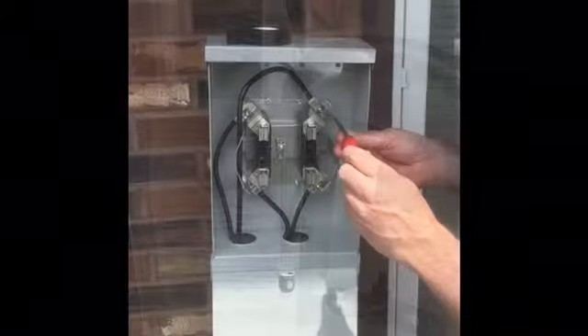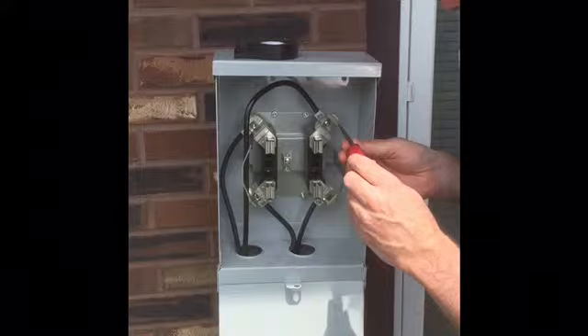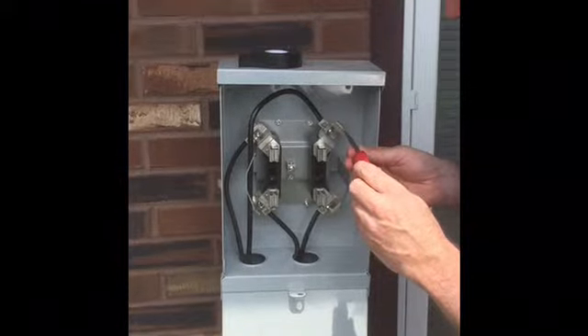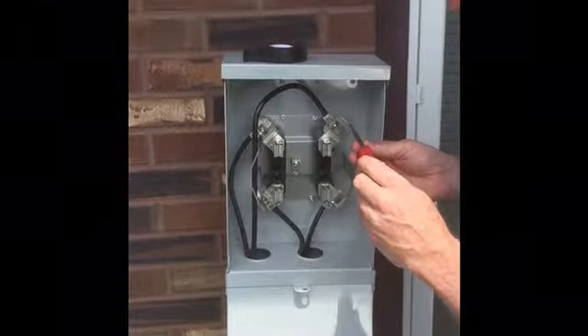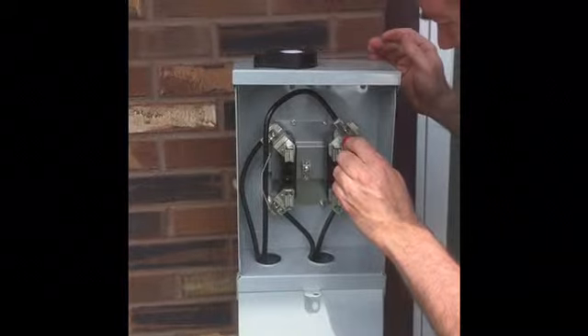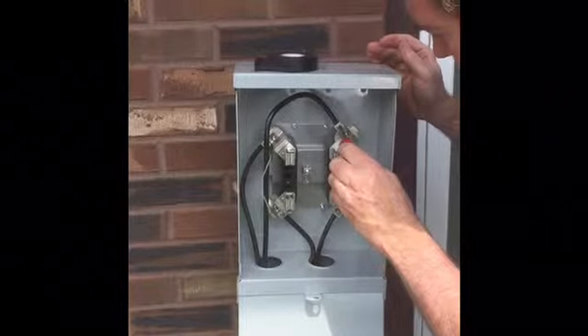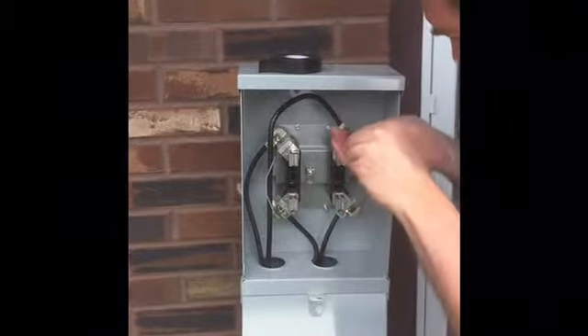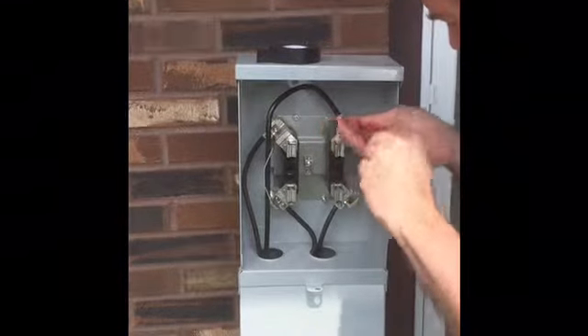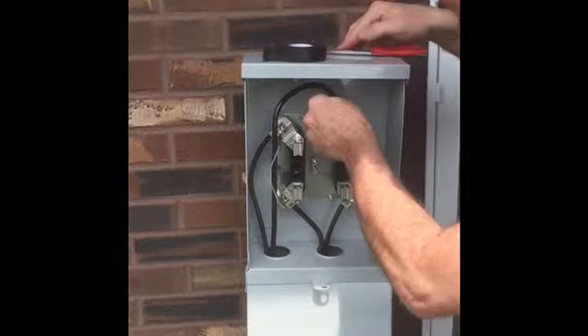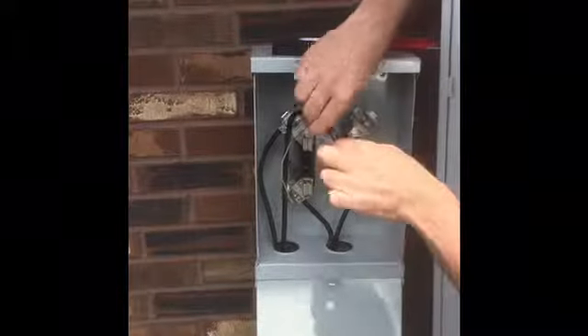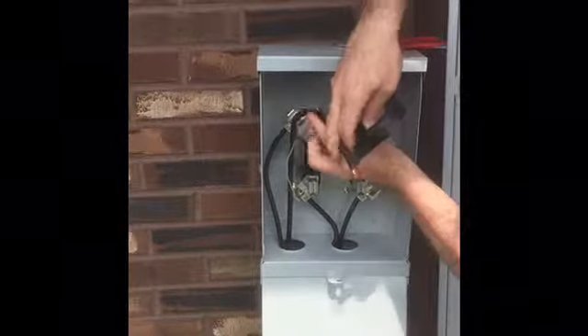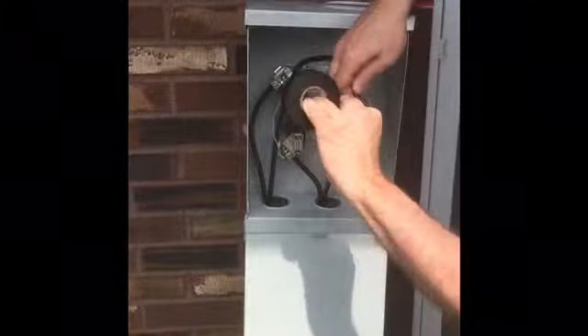See on this step, basically what we've got to do is, after the bad leg is identified, you need to remove that from the line side of the meter socket, and then we're going to tape that off. So the whole point of taping it off is to prevent any chance of backfeed.